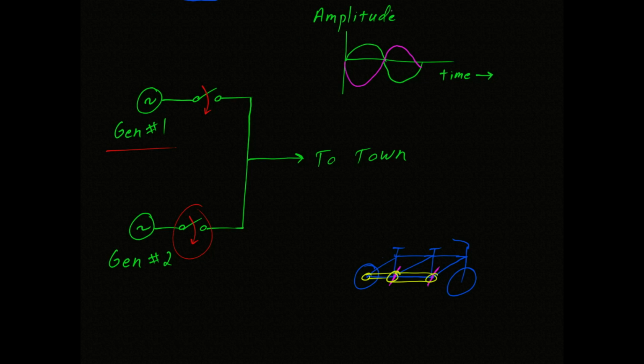You end up with the same situation with the generator. We have to be careful because generator number 2's voltage could be anywhere. Maybe it's in phase like this, or maybe it's completely out of phase, or maybe somewhere in between, and we have to be careful that we close the breaker at the right time. You could have one generator at a positive maximum and the other at a negative maximum. This is a bad situation—they're effectively shorting each other out.